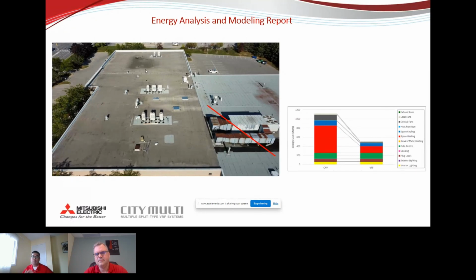And we don't just do offices, we also do high-rise buildings, low-rise buildings, so the pipe size and pipe length is usually not a big issue. Also, the more pipe you use, the longer it is, the more expensive your project may be, as well as more refrigerant you're going to use. So it's more of a strategic investigation that we need to do.